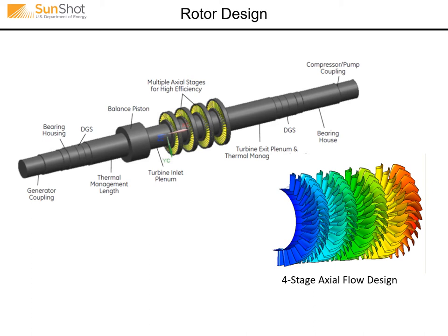Because of the high exhaust pressure of 84 bar, we use mechanical dry gas seals — very common in the oil and gas industry. These are face seals operating on a very thin fluid film of the gas itself. A buffering gas is injected to ensure the gas is clean and at the proper temperature. The bearings are tilting pad type oil bearings, as well as a tilting pad type thrust bearing, large enough to accommodate traditional fluid film bearings used in power generation and oil and gas.